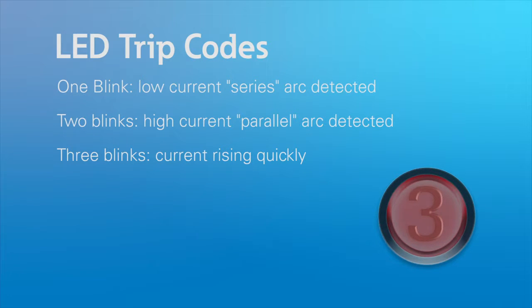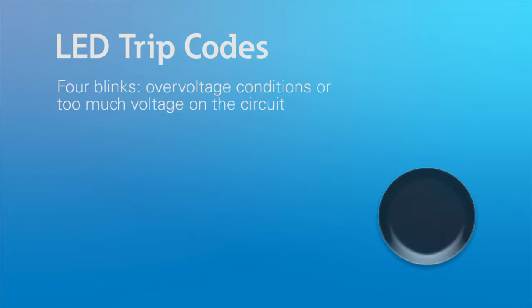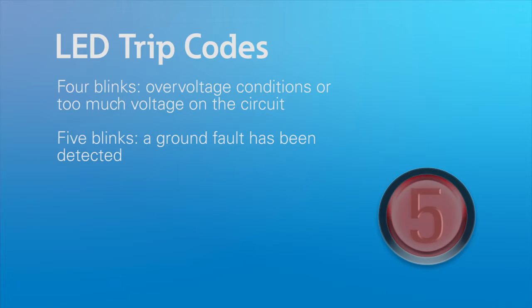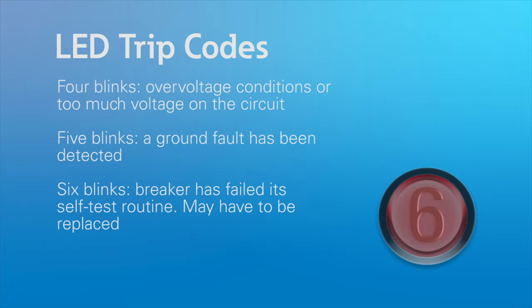3 blinks. The electronics of the breaker see the current rising quickly, indicating a short circuit in the electrical system. 4 blinks. The breaker identifies an overvoltage condition or too much voltage on the circuit. 5 blinks. The breaker has detected a ground fault. 6 blinks. The breaker has failed its self-test routine and may have to be replaced.